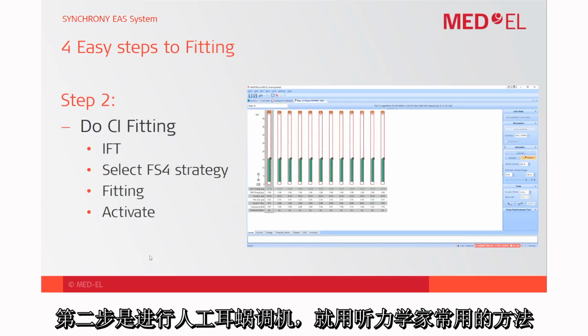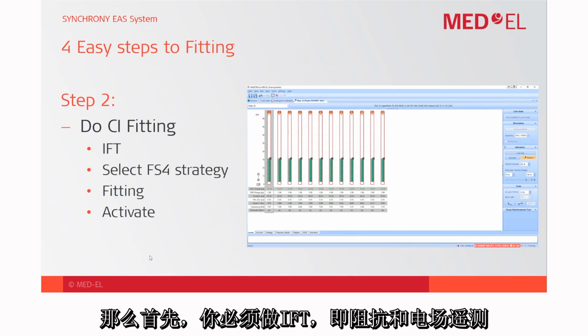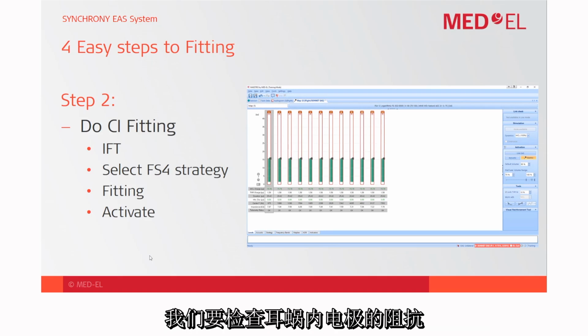So this is done in the background and the clinician doesn't have to do anything. Step 2 is doing the cochlear implant fitting just the usual way the audiologist would do. So first you have to do the IFT, which is the impedance and field telemetry. So we check for the impedance of the electrodes inside the cochlea. Then we select the fine structure 4 strategy.